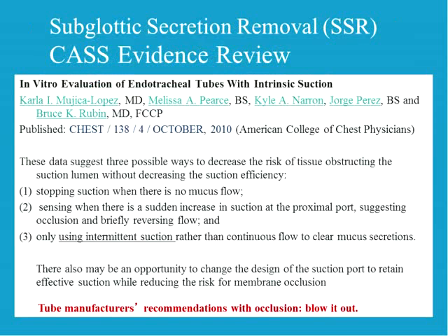Sensing when there's a sudden rise in suction at the proximal port and briefly reversing the flow. So in other words, whenever the device would sense that there's pressure building up, it actually would purge it or blow it out. And then using intermittent suctioning rather than continuous flow to clear mucus secretions. And that recommendation actually has been adopted. Most all the manufacturers of these subglottic secretion endotracheal tubes have adopted that.